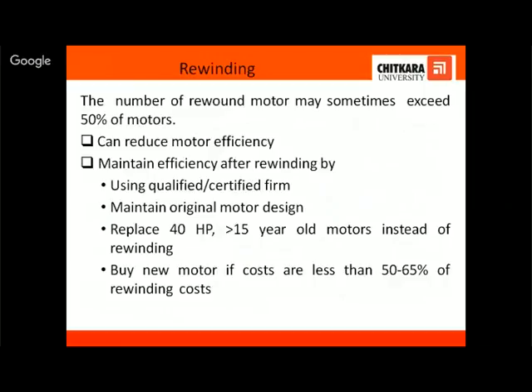Now the next point is the rewinding of the motor. Sometimes it happens that in the industry, more than 50% of the motors are rewound motors. Now what happens with the rewinding of the motors? They reduce the motor efficiency. Now if the rewound motor has to be used, then there are certain instructions.